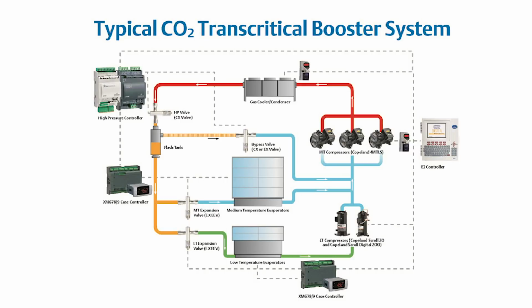Now, quickly, if you look at this diagram, you're going to notice down at the bottom right side of the diagram, you have the scroll compressors. And the scroll compressors are the compressors for the low temperature part of the system, so your freezers in this grocery application. But rather than having their own condensers like you would often have, instead these compressors discharge into the suction of the medium temp compressors. And so you see you have the scroll compressors on low temp and you have semi-hermetics on the medium temp, which is exactly what Kevin is describing here.